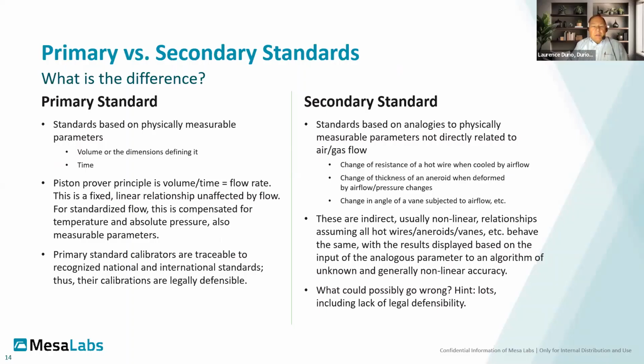As I said, physically measurable parameters, typically volume or the dimensions defining it, and time. A piston prover is basically a piston going up a cylinder. So it's the volume of the cylinder divided by the time that gives us a flow rate. It's fixed, it's linear, it's unaffected by the flow rate within any reasonable limits. We can standardize that flow by compensating for temperature and also absolute pressure, both of which are also measurable, traceable parameters. As we said, traceable to international and national standards.